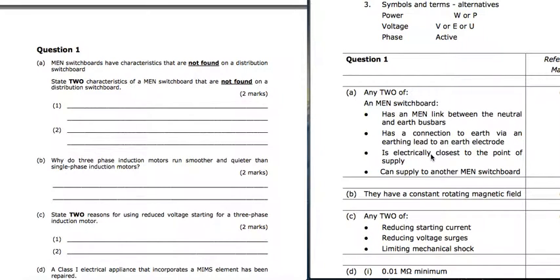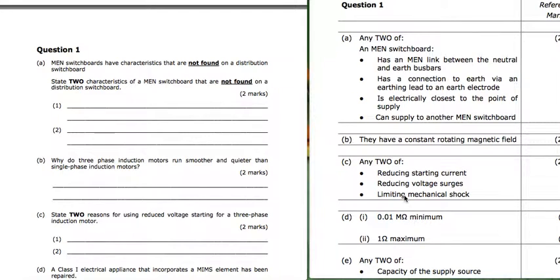It's closest electrically to the point of supply, and it can supply another MEN switchboard. I think the first two are the easiest to remember, the MEN link and the earth via the earthing lead to the electrode. B. Why do three-phase induction motors run smoother and quieter than single-phase induction motors? Well, it's all about that rotating magnetic field. They have a constant rotating magnetic field.